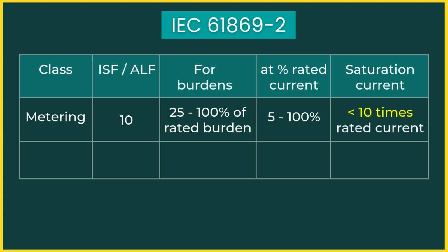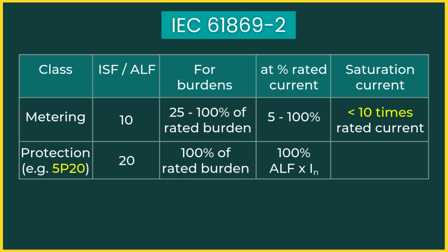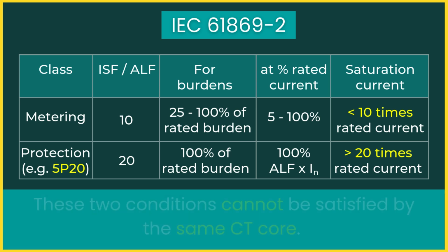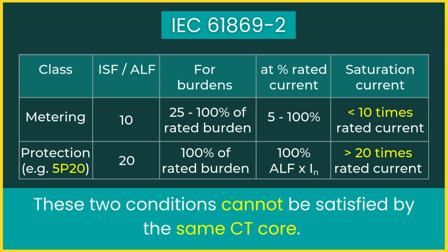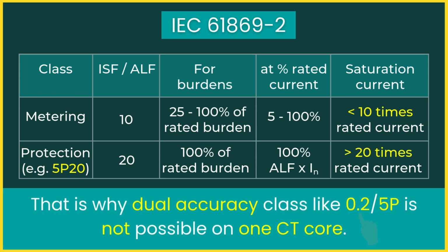On the other hand, a protection class CT with accuracy limit factor 20 must meet its specified accuracy limits for 100% of rated burden, and must not saturate up to 20 times rated current during faults. So the metering core demands early saturation, while the protection core demands no saturation up to very high current. These two conditions cannot be satisfied by the same CT core. That is why dual accuracy class like 0.2 and 5P is not possible on one CT core.